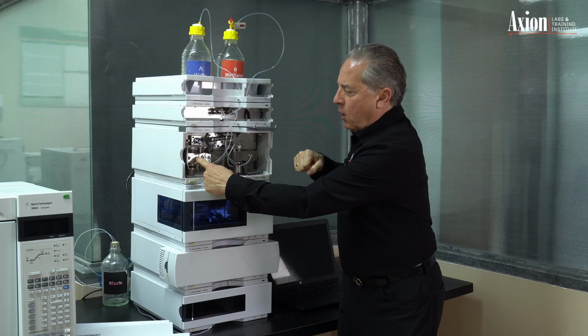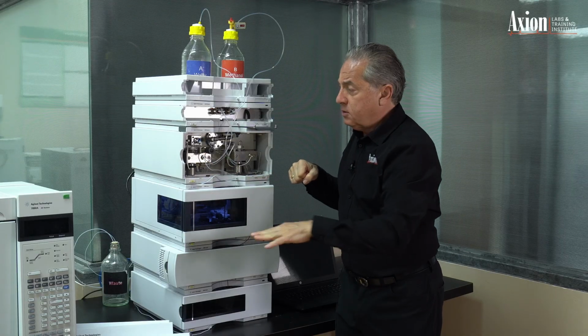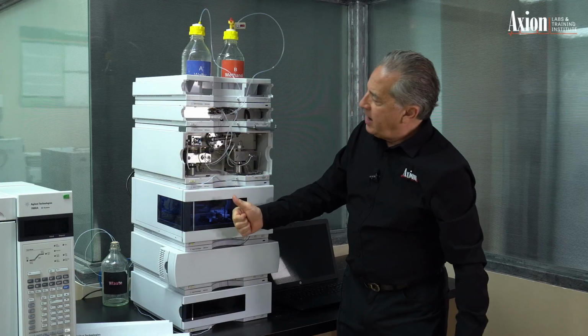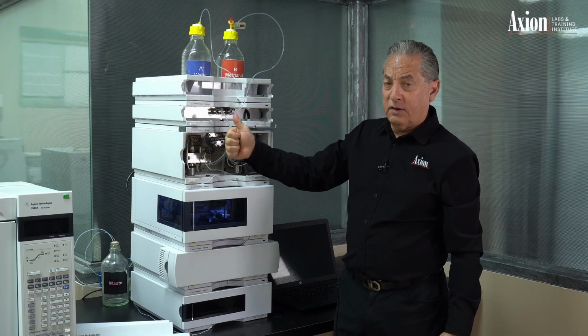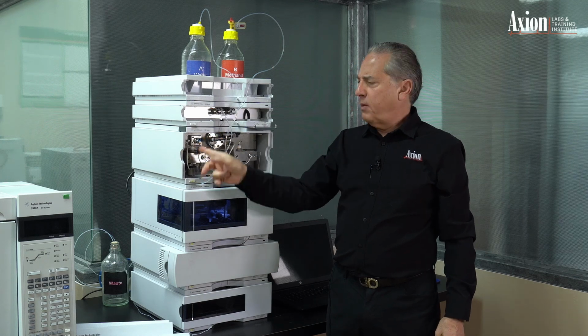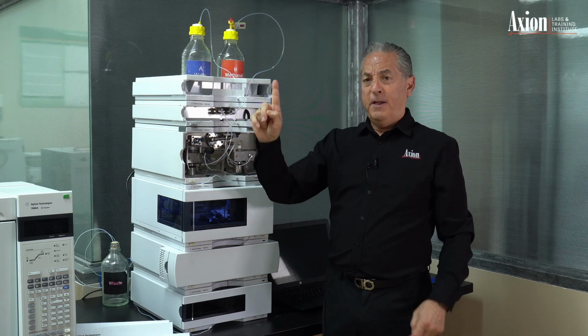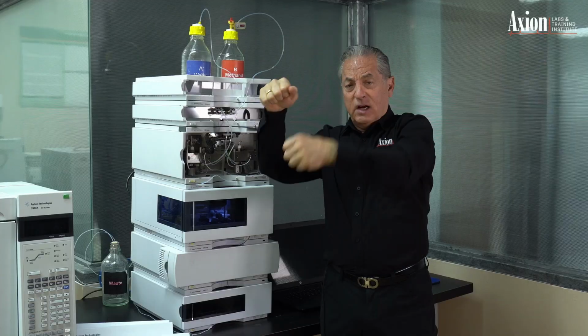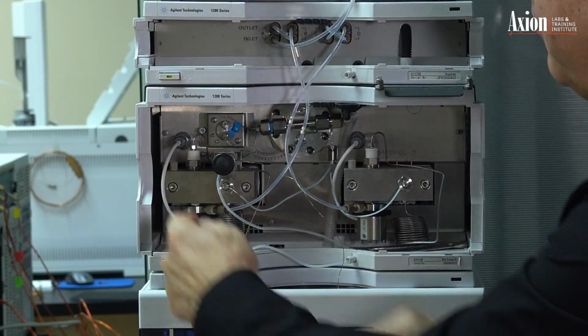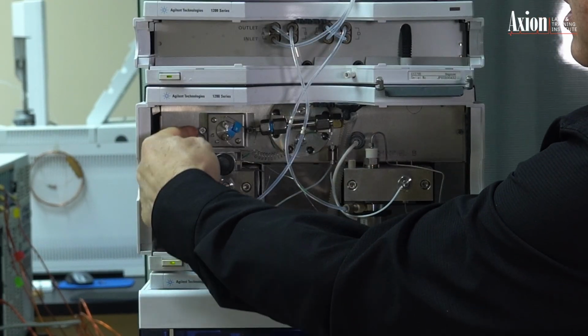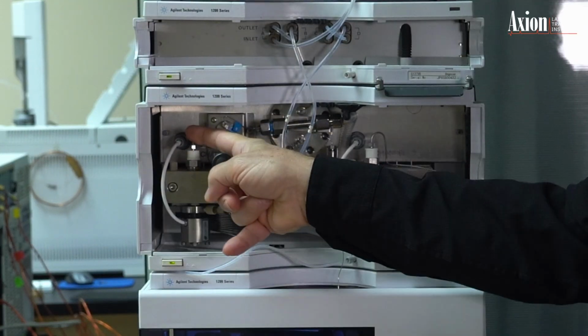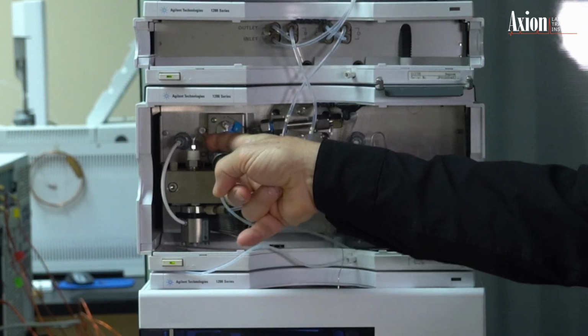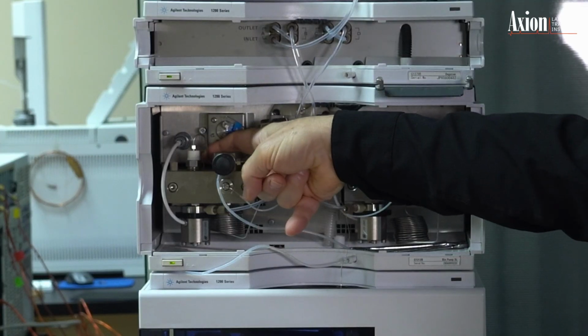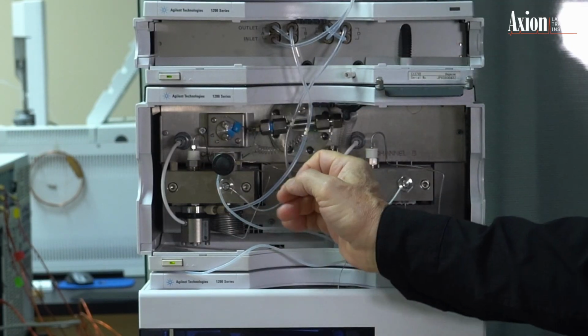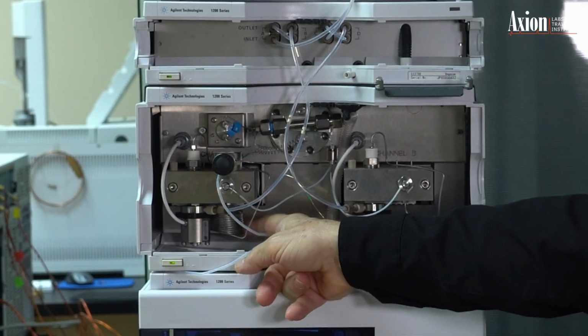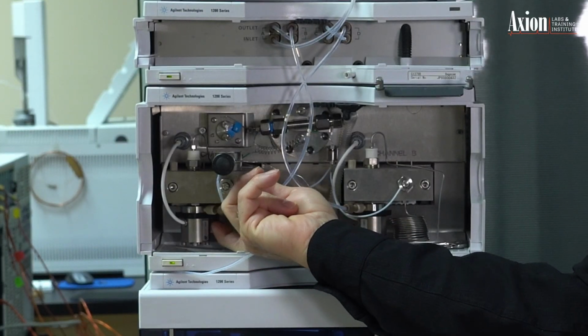and then when it pushes forward, the inlet valve locks closed, the outlet valve opens, and it pushes mobile phase out the outlet valve. And this is just based on pressure. If I put enough pressure on this side, I can push up. If I put pressure on the other side, remember, it's going to close off. So now I have high pressure flow coming out of piston number 1, and if you could see, I have stainless steel tubing. This is now high pressure. From here, it's a little hard to follow, but this piece of tubing actually dips down underneath the pump head and it enters into piston 2.